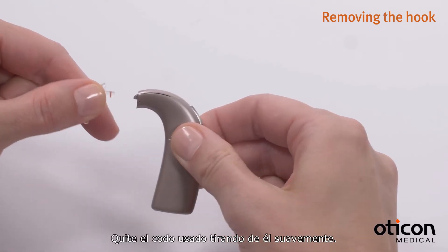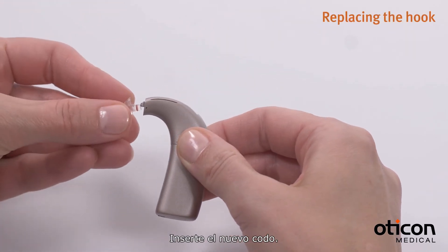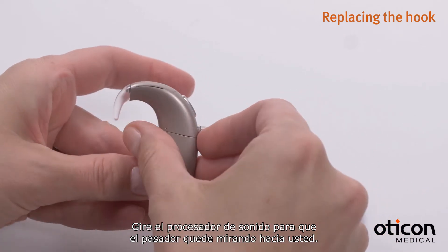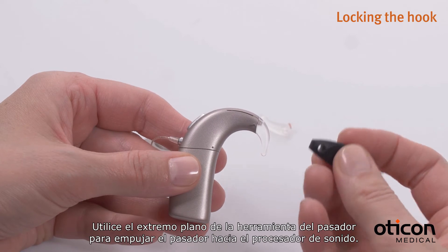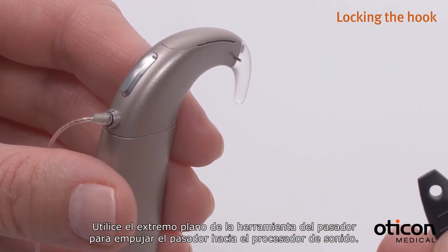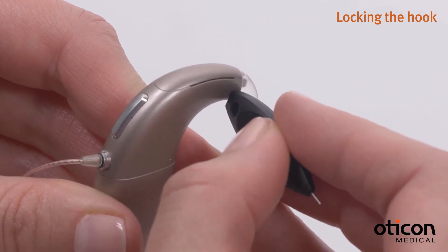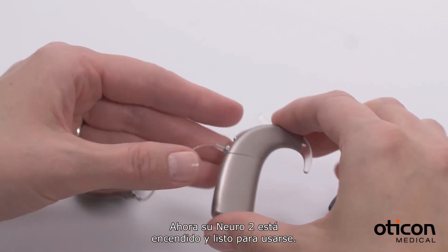Remove the used hook by pulling it gently. Insert the new hook. Turn the sound processor so the pin is facing you, then use the flat end of the pin tool to push the pin back into the sound processor. Your Neuro 2 is now ready for use.